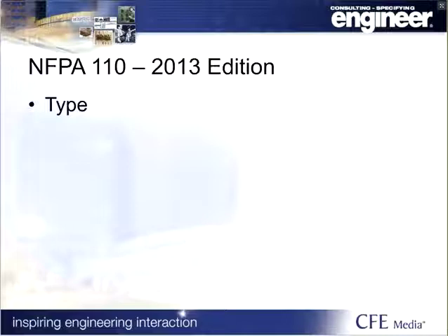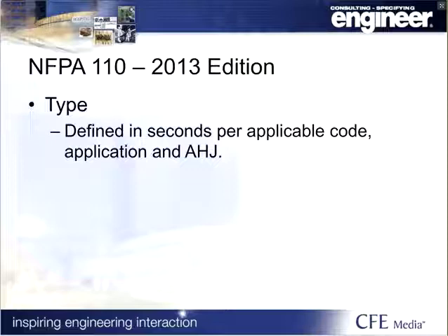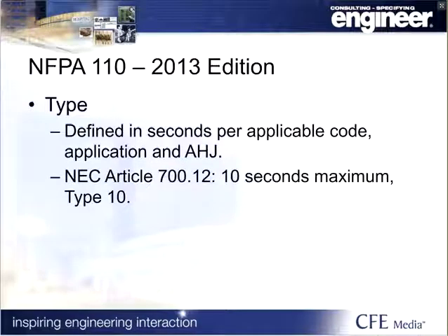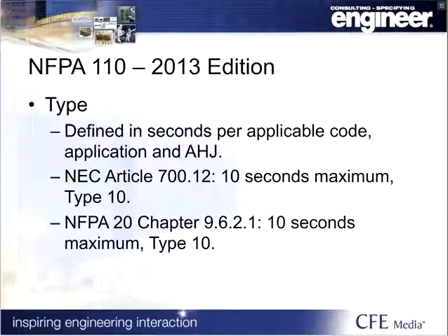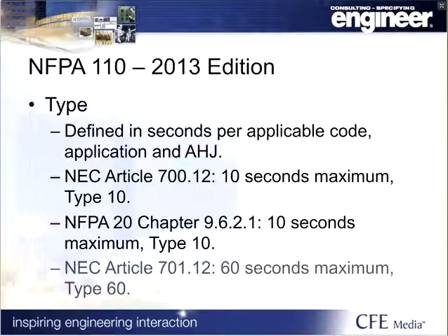Chapter 4.3 defines the system type in seconds. This is the maximum time allowed by the applicable code to start up, synchronize, and transfer or pick up the load. Emergency systems under NEC 700 are required to be energized within 10 seconds. The type would be 10 in this case. NFPA 20 for fire pumps also requires no more than 10 seconds. And the last example, code-required or legally required standby systems under NEC Article 701 are allowed up to 60 seconds to be energized.